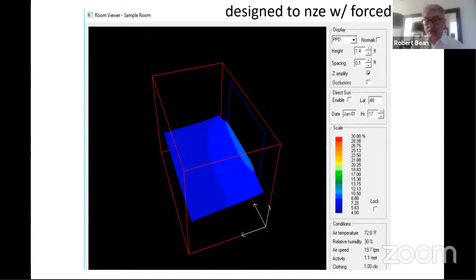So all I've done is taken these three models, simulations, and plotted them. You can present this to the architect and client and say, if you look at the left side, we're not in compliance with ASHRAE standard 55. The reason is we have a high window to wall ratio, poor performing glass, poor architecture, poor enclosure design, and poor choice in HVAC systems. The combination leads to a lot of people complaining about the space, and it's not in compliance with the standard.